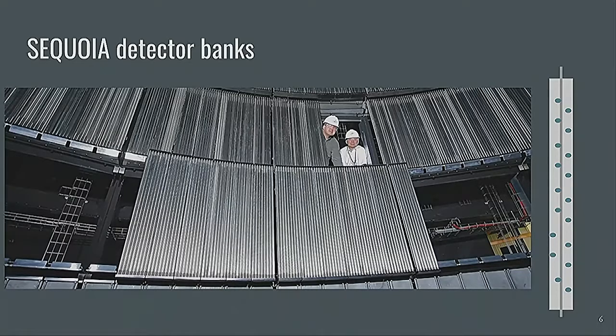These detectors allow for Q resolution because you can see exactly where on each tube your neutron hits. The neutron will come in, interact with these helium little circles that I've drawn, generate a current, and go through that wire. That's that long gray line. And depending on where they interact with the wire, you will have a different voltage reading because of the resistance that you have to go through between where the neutron is interacting and the end of your detector. So to kind of summarize the slide, this detector bank is really cool.